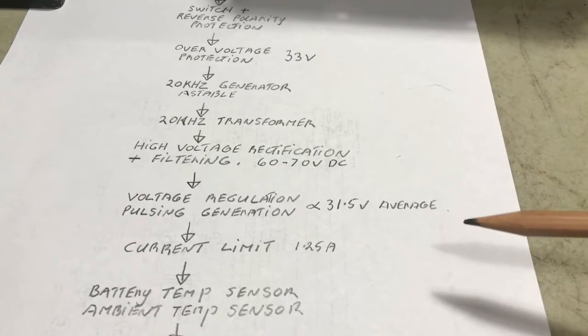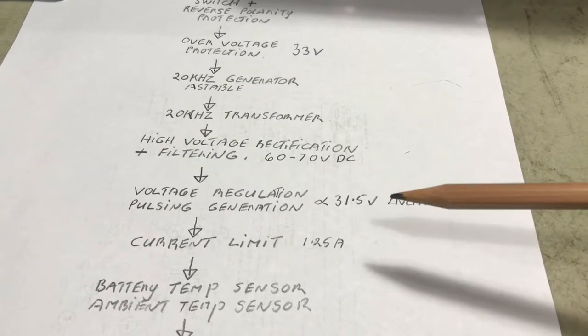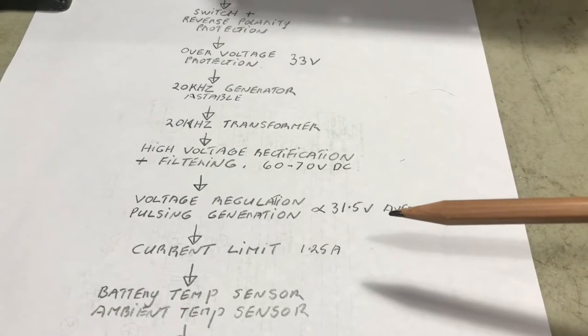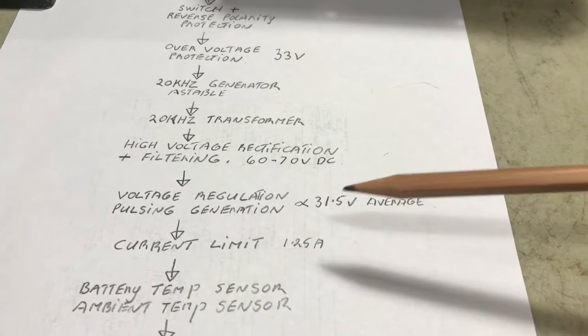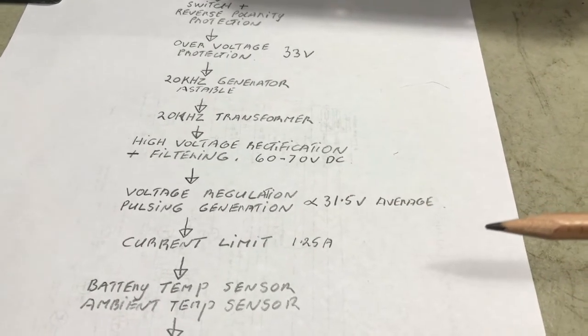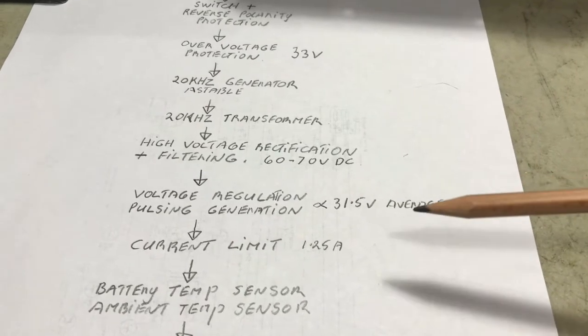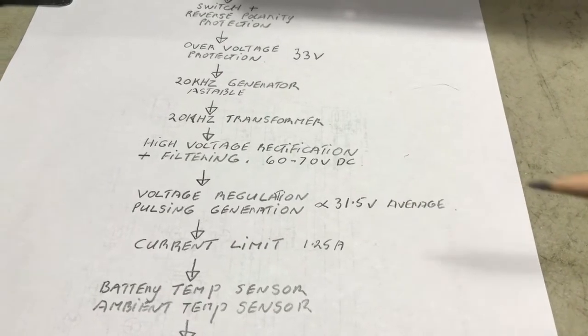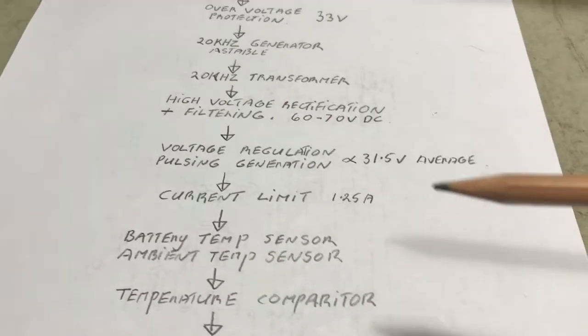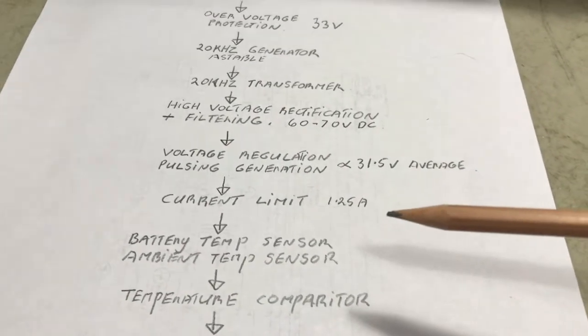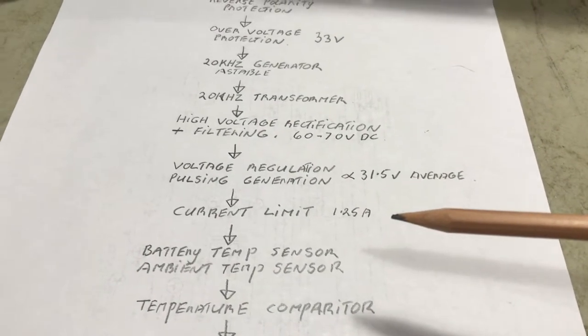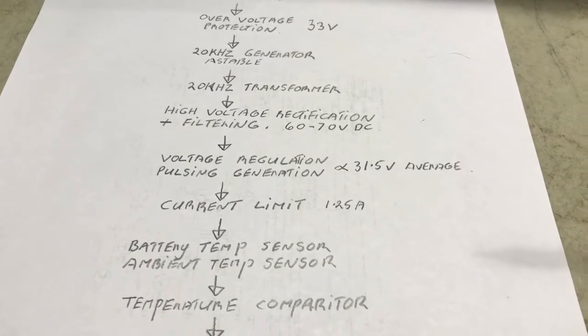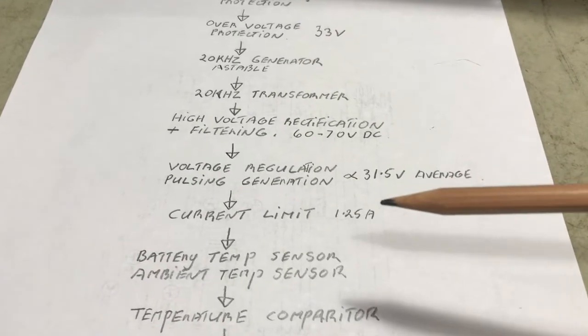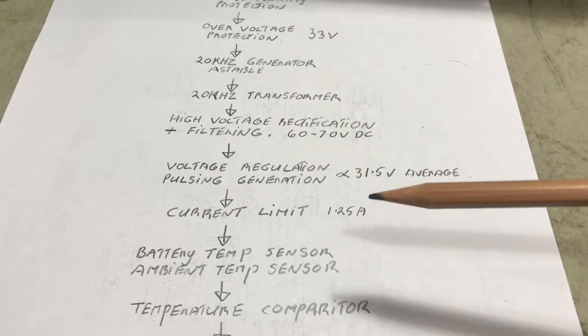The mean voltage there is about 31.5. So as the voltage rises during charging, it gets up to about this level and won't go any higher. That's the regulator, set at the highest voltage. And then there's a current limit in the unit which limits the charge current to 1.25 amps, and that's pretty constant through the whole charge cycle.